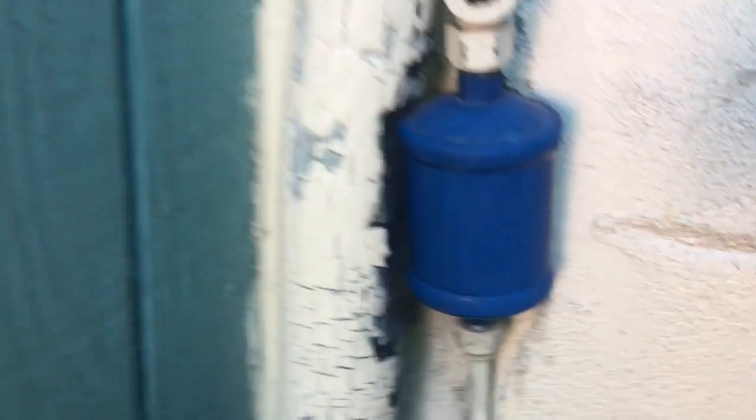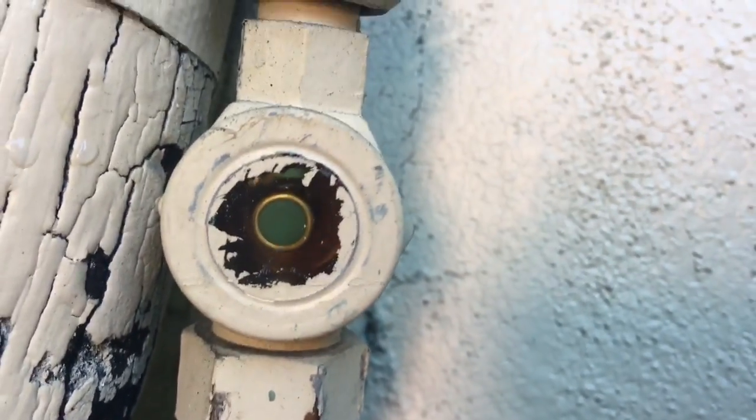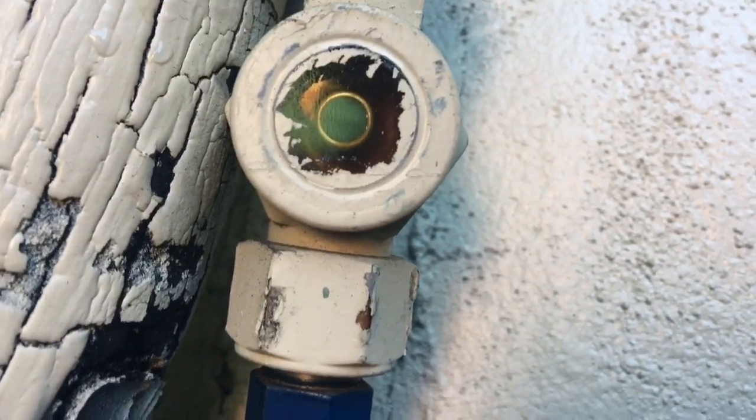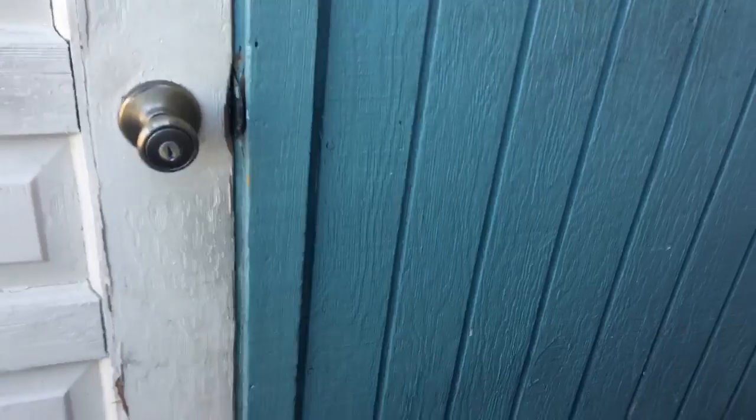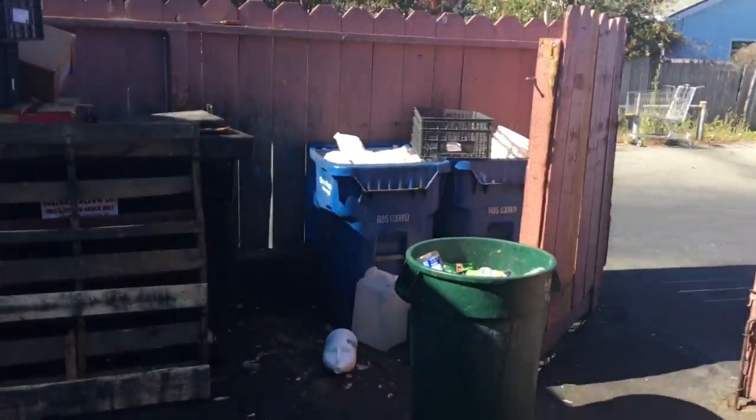Let's go inside the box and see what the temp is. See how our sight glass is looking? A couple little bubbles in there. I'm going to see if the TXV settles down. It's pretty clear now — not bad. These guys have been leaving the door open and it's driving me nuts. Let's go take a look.